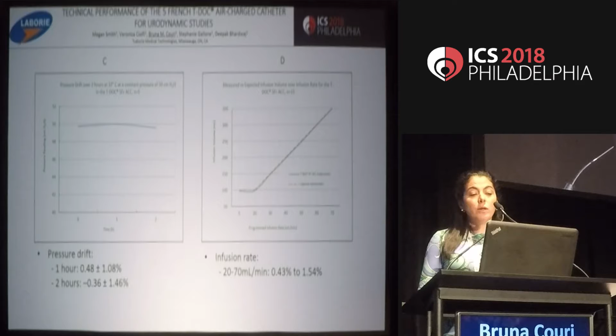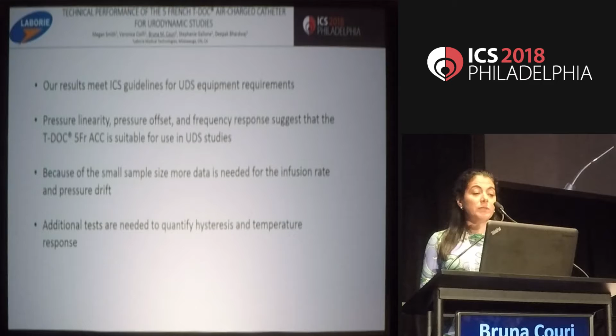In summary, our results meet the ICS guidelines for UDS equipment requirements. Pressure linearity, pressure offset, and frequency response suggest that TDOC 5-French air charge catheter could be used for urodynamic studies. Because of the small sample size, more data is needed for the infusion rate and pressure drift. Additional tests are needed to quantify hysteresis and temperature response.